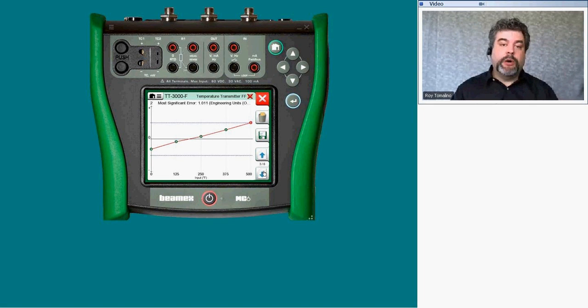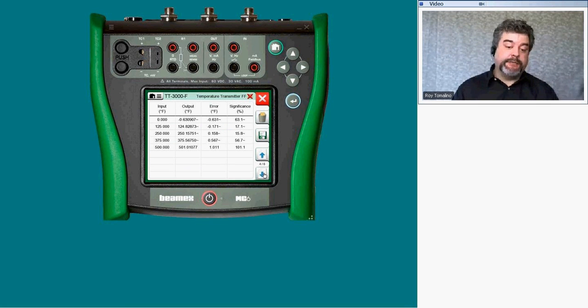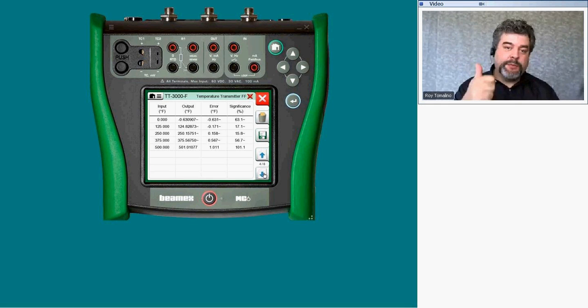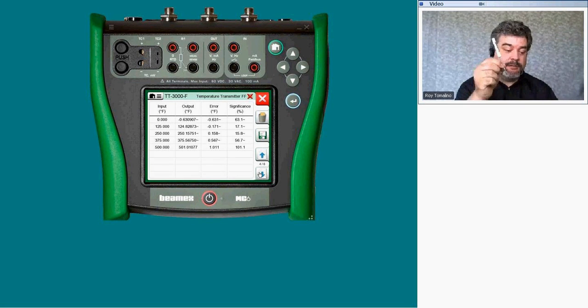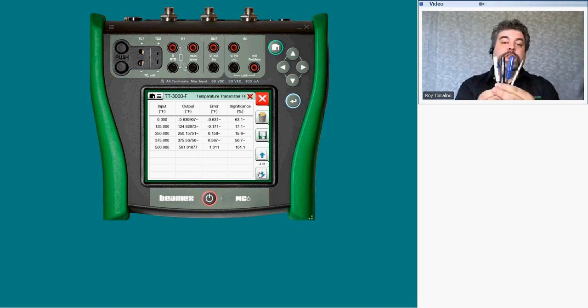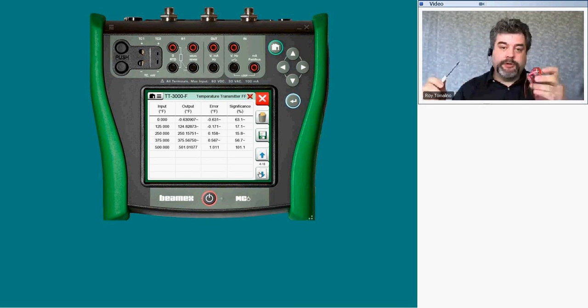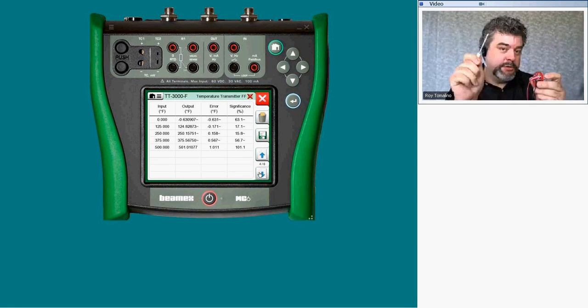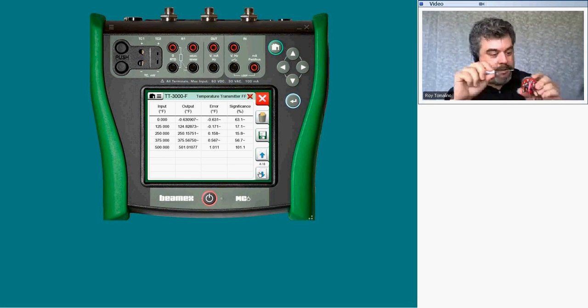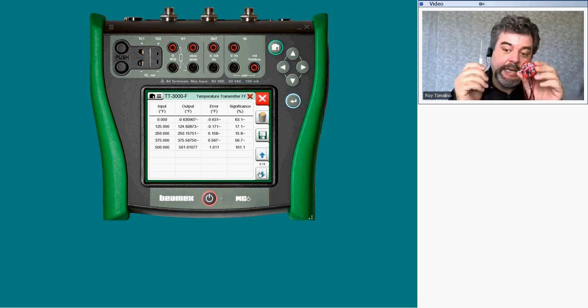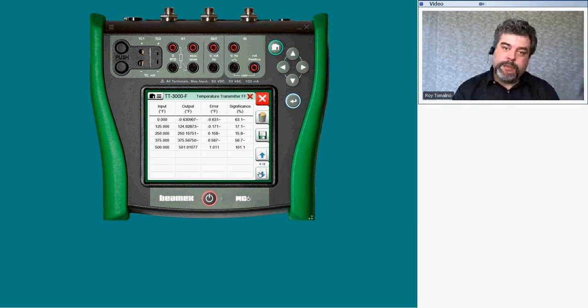My maximum error was 1.011 degrees Fahrenheit, and I had a tolerance of one degree. So the entire test — all test points needed to be within plus or minus one degree. Let's take a closer look at the data. Here's the graph, a visual of what we had. If I hit the down arrow one more time, we'll see the raw data itself. My first test point was 0.6 degrees off in the negative direction. So I have a problem with my zero, and I also have a problem with my span. On an old conventional transmitter, we used tweakers — they have a small flathead design and you adjust the zero pot or potentiometer. But there is no potentiometer here. You cannot change this with a screwdriver. This is a smart instrument. You need something with a communicator — something that can talk to HART, Foundation Fieldbus, or Profibus to make this happen.